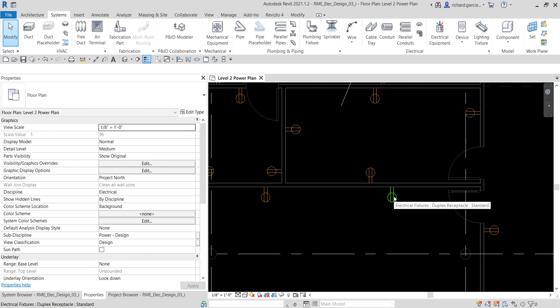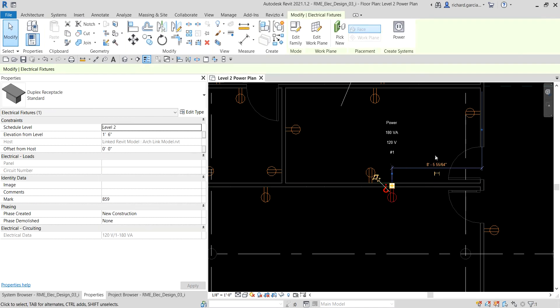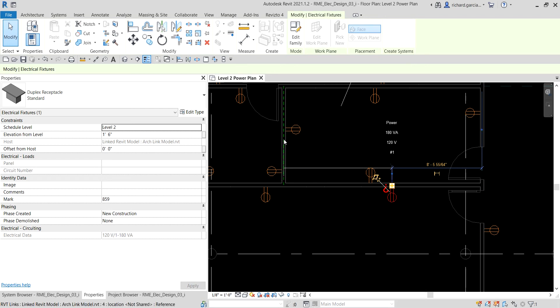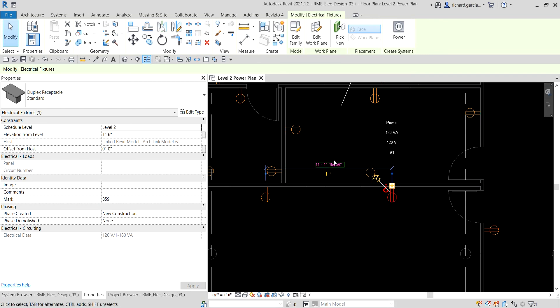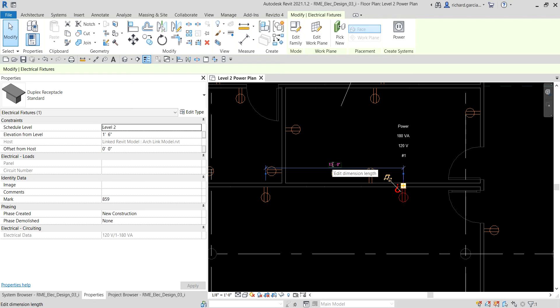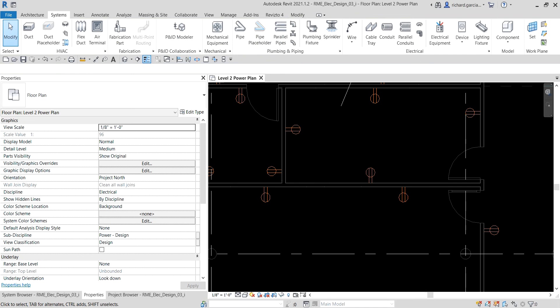When you click a wall-hosted duplex receptacle, a temporary dimension appears. You can click that dimension and type a distance value to reposition it. Alternatively, click the blue 'Move Witness Line' node and drag it to align with another receptacle, then click the temporary dimension and type a distance — for example, 13 feet — and press Enter. The receptacle is now positioned at 13 feet. You can drag the witness line to reposition the reference.